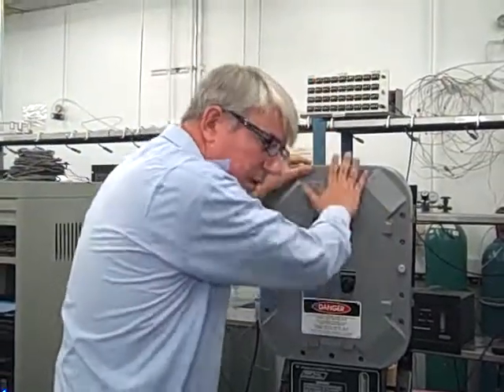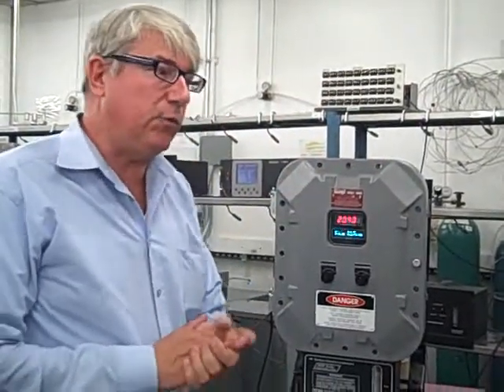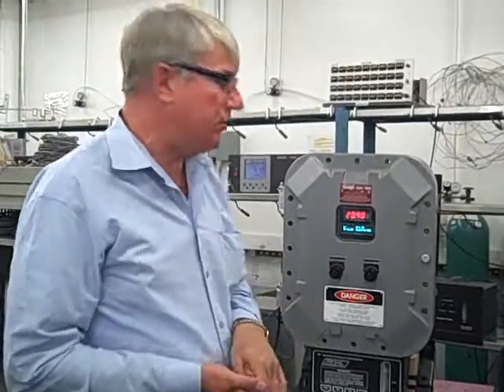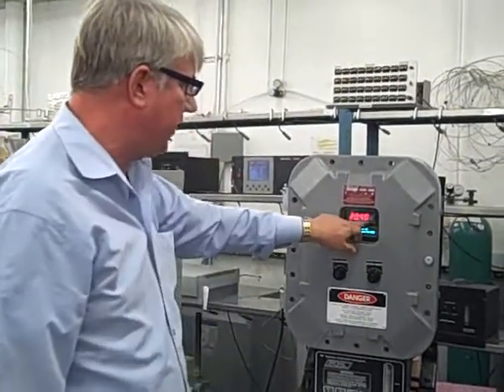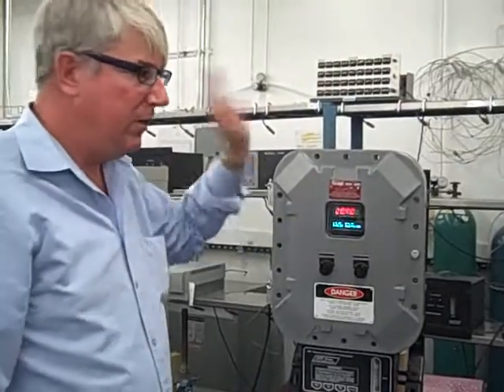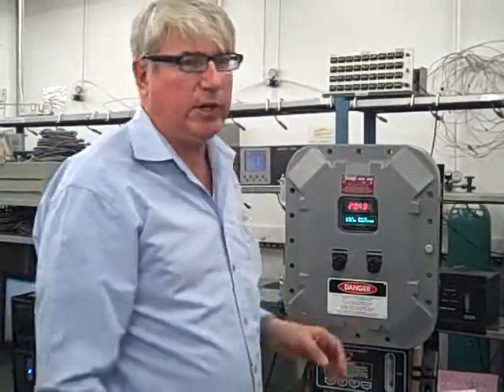For a percent oxygen sensor, it has a different way that it malfunctions at the end of life, which is it just loses output. So all of a sudden you may be reading 20.9 or 10%, you come in, it's just reading 0.